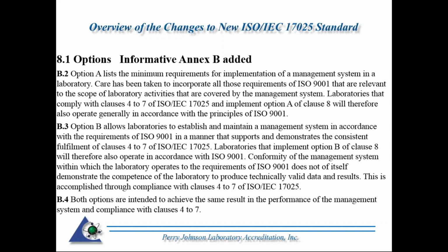We also have Option B. Option B allows laboratories to establish and maintain a management system in accordance with the requirements of 9001 in a manner that supports and demonstrates the consistent fulfillment of Clauses 4 through 7 of 17025. Laboratories that implement Option B of Clause 8 will therefore also operate in accordance with 9001.